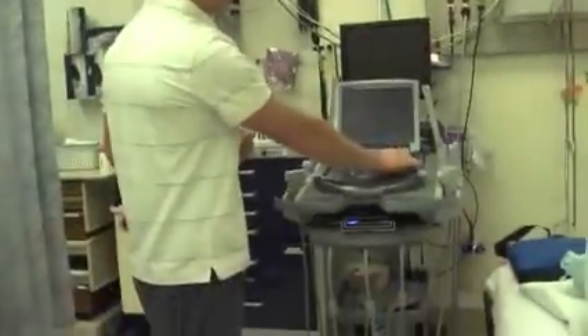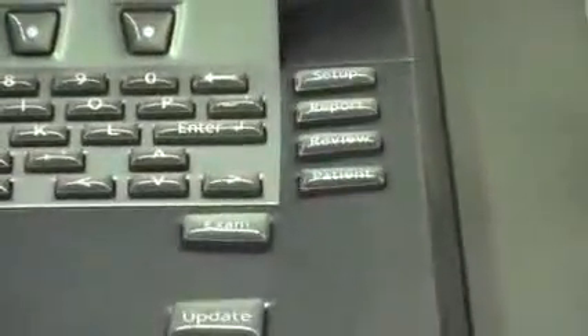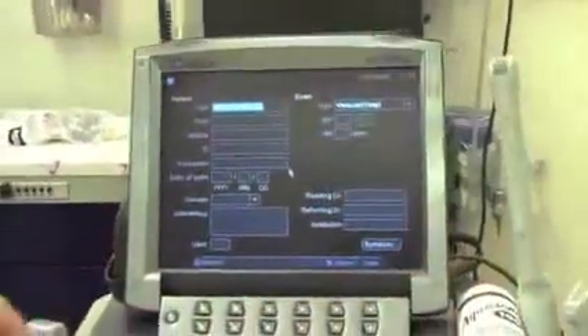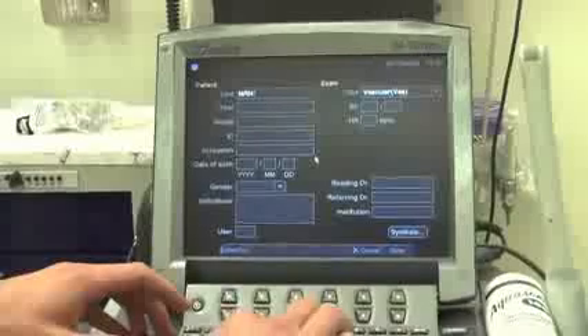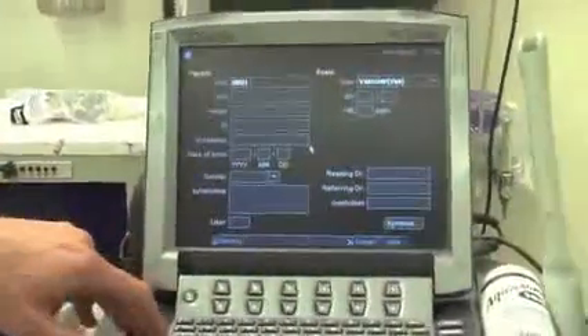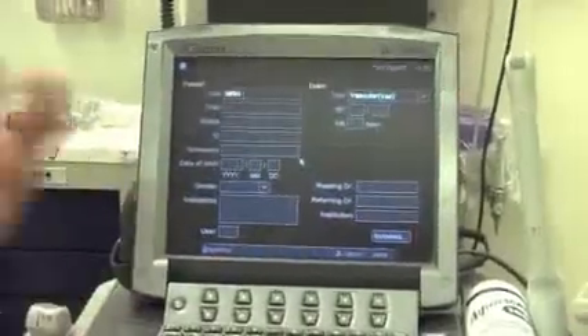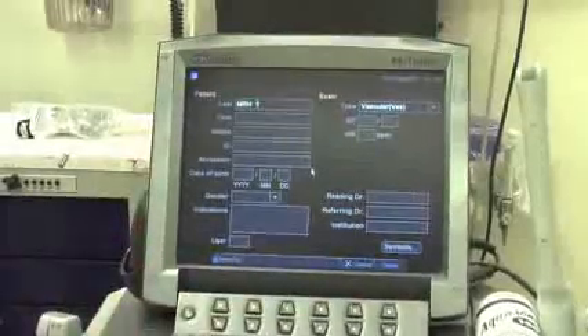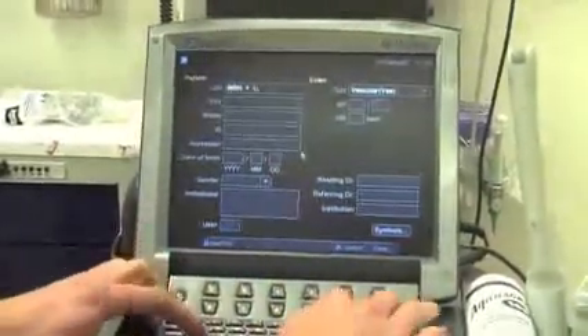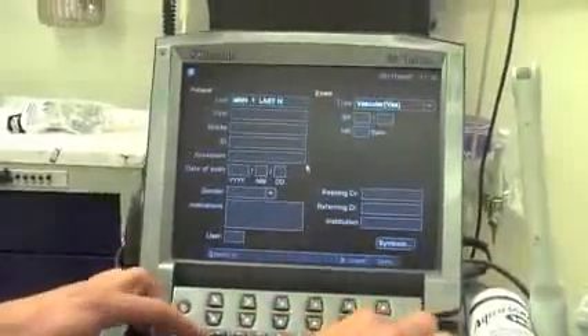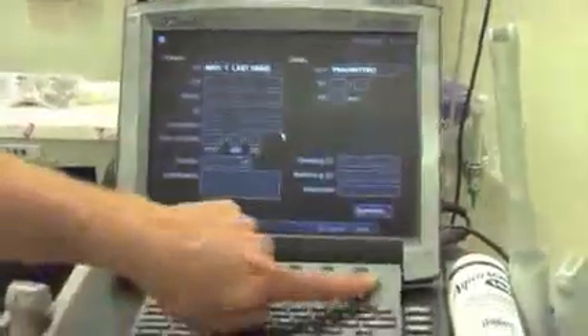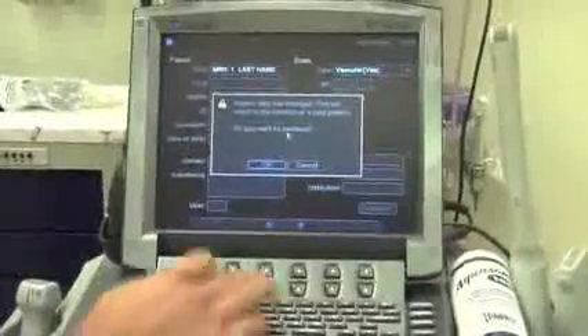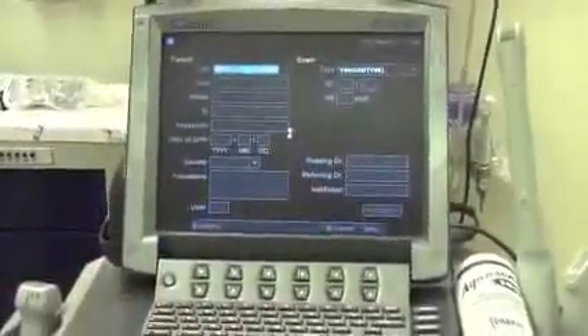but before that, what we need to do is enter the patient information into the machine. So you're going to come over and hit this patient button here, and that's going to get you into the form to input your patient information. So the first thing you're going to put in is the patient's medical record number, then a couple of spaces, and then you're going to obtain the patient number from the data collection sheet, whether it's 1, 2, 3, etc. So for these purposes, we'll just say it's patient number 1, and then you want to input your last name as the person performing the ultrasound. Once you're done, you can hit this hotkey for done, hit OK. And then you're ready to perform the ultrasound.